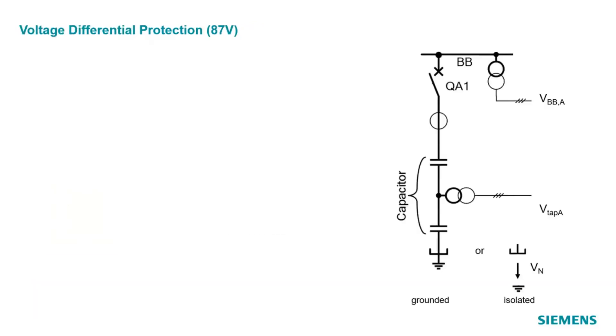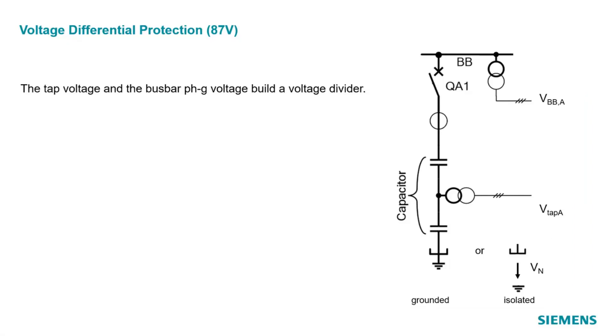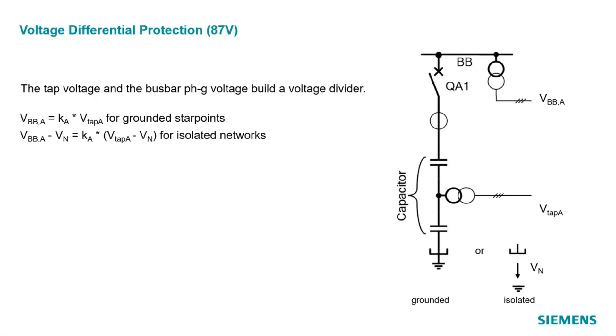The voltage differential protection is suitable for capacitor banks with both grounded and isolated star points. The tap voltage and the bus bar phase-to-ground voltage for each phase build a voltage divider. The bus bar phase-to-ground voltages can be calculated by multiplying the tap voltages with a quotient of the capacitances, Ka. If the star point is isolated, the neutral voltage also needs to be considered. The differential voltage V_diffA for phase A is set up according to the shown formulae, and for phases B and C the formulae are equivalent. If the system is balanced and there is no faulty capacitor element, the differential voltage is exactly zero. In reality, manufacturing tolerances, temperature drift, and aging can cause a differential voltage. Depending on the topology and number of capacitor elements, the measured voltage difference for a single defect can be very low, and the operational differential voltage could disturb and mislead the differential protection.